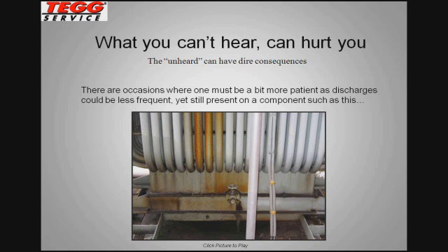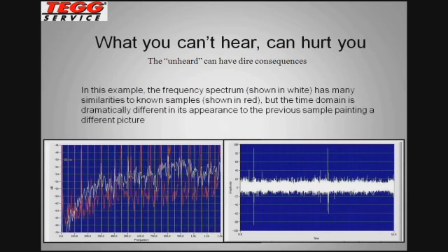At 1.5 seconds and 9.5 seconds of the recording, if you've ever used the contact module and you move the instrument, you may hear something in the probe. It sounded just like that, but being very still, we knew that we had not moved the probe, and there were 2 discharges that occurred over a 30-second recording. I'm going to pull up here the frequency and time domain view of that particular recording.